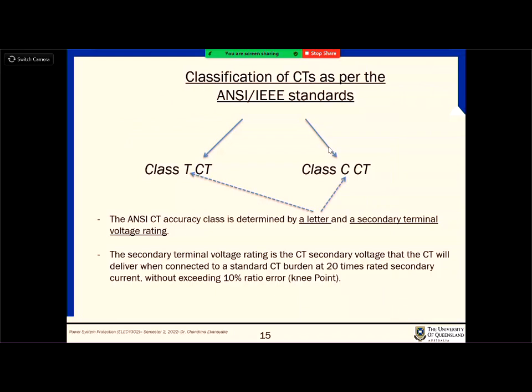Okay, so when you're looking at CTs, there are two main classes specified by the IEEE standards, Class T and Class C, right? What are the differences between them? We will quickly go through them. The standards define the accuracy class by a letter, and they also give you the secondary voltage ratings, because that relates to the insulation. It's not important for our calculations, but it is important in reality for applications in the system.